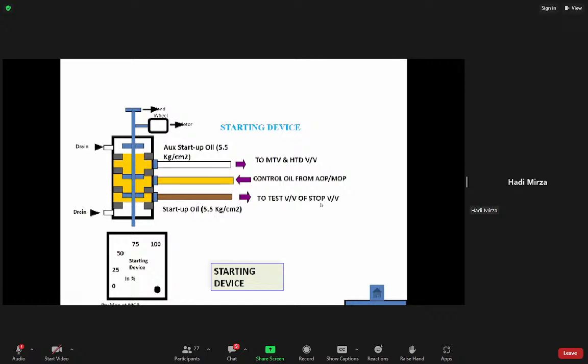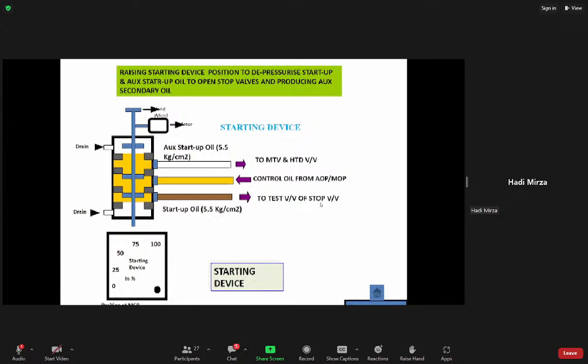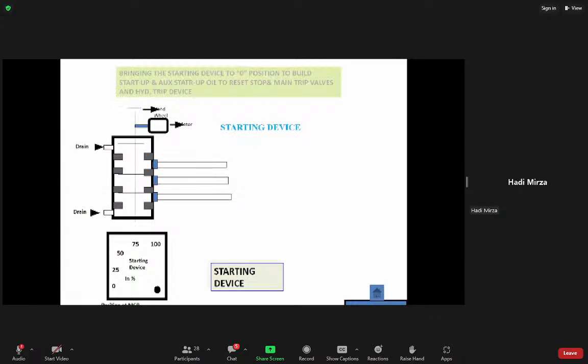Once it goes completely to the 0 position, it will reset the valves and trip devices. When you go from 0 to 100, it will operate the stop valves and open them. Around 30 to 45% of starting device opening, the stop valves will be operated. Then complete opening of the valves will be done.